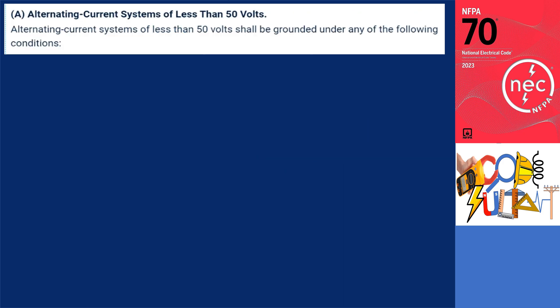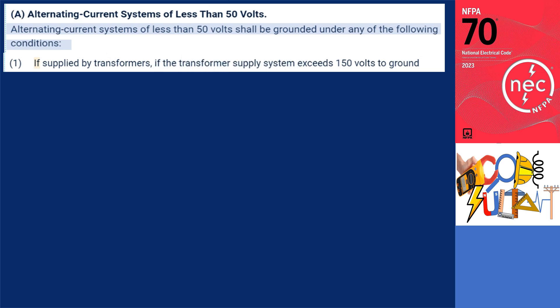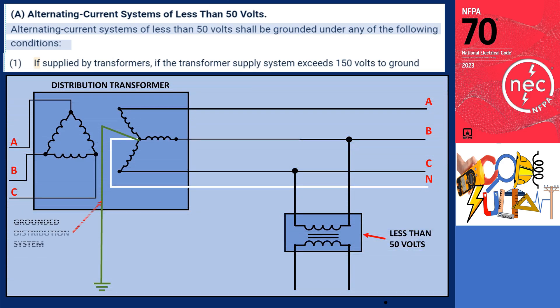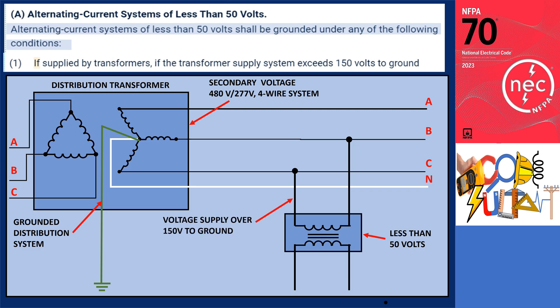What are the alternating current systems that shall be grounded? Section 250.20A requires alternating current systems of less than 50 volts shall be grounded under any of the following conditions. Condition 1: if supplied by transformers, if the transformer supply system exceeds 150 volts to ground. To illustrate this, let's consider a grounded distribution system with a secondary voltage of 480 volts for three-phase and 277 volts for single phase. As the supply voltage exceeds 150 volts to ground, one of the transformer's secondary conductors must be connected to the ground.